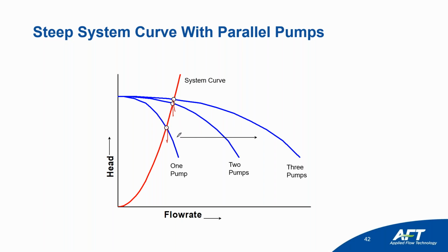So what you need to do is, if you have a lot of friction in your system here, you've got to change your system. Maybe you have to go in and do a retrofit. Maybe you need to do some larger pipe diameters throughout your system, because if you want to get more flow, your velocities are going to go up. So for higher velocities, you get higher pressure losses, and that's going to cause problems.